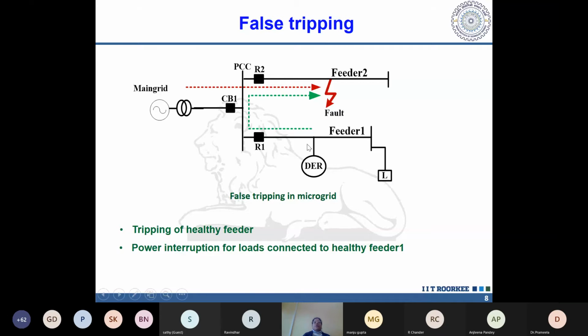Due to this fault inception, this DER will try to supply some fault current to this point, and as well as this red dotted line, the main grid also will try to supply some fault current. So in this process, relay R1, which is protecting feeder 1, and overcurrent relay R2, which is protecting feeder 2, both will see some fault current. Because the fault is in feeder 2, R2 will sense that there is a fault in my feeder 2, give a trip signal, and the circuit breaker will open feeder 2. However, at the same time, R1 will not remain silent.